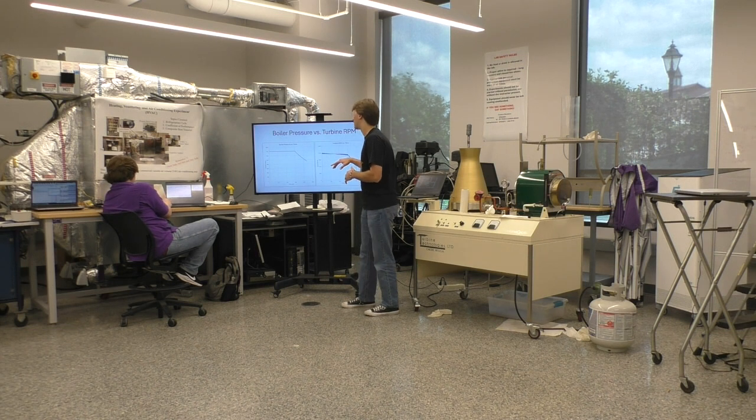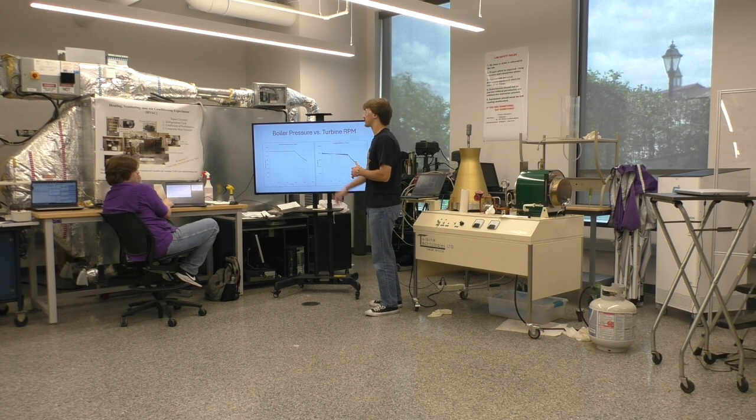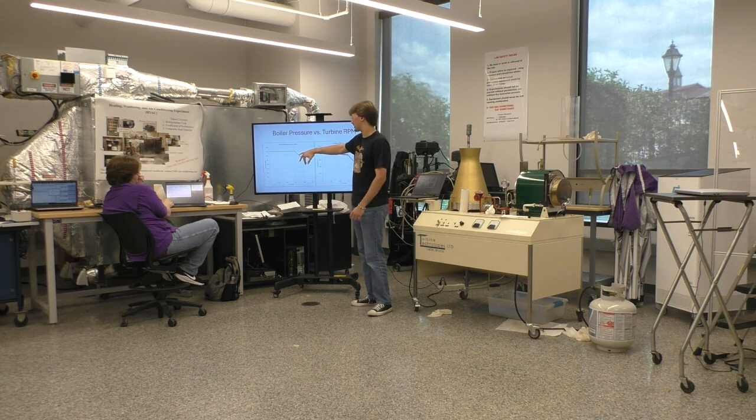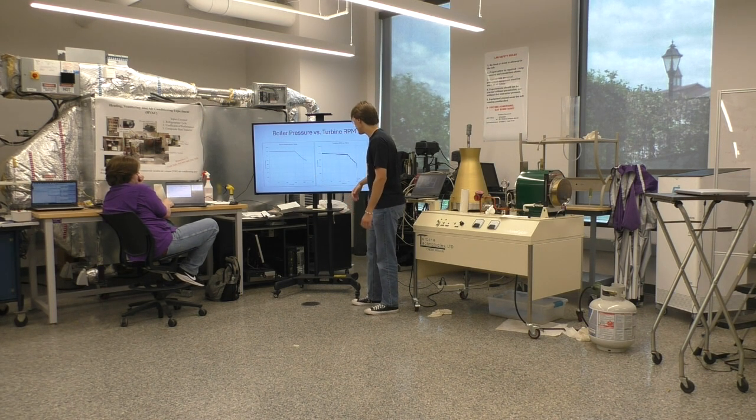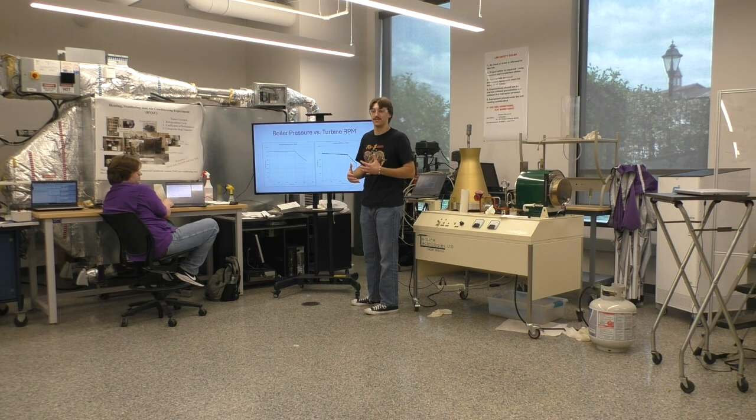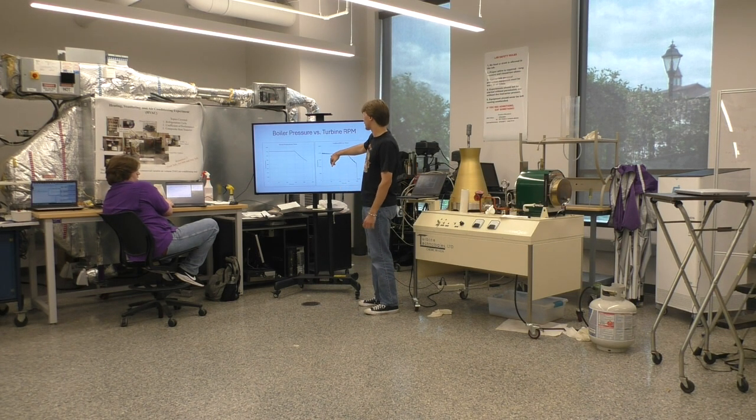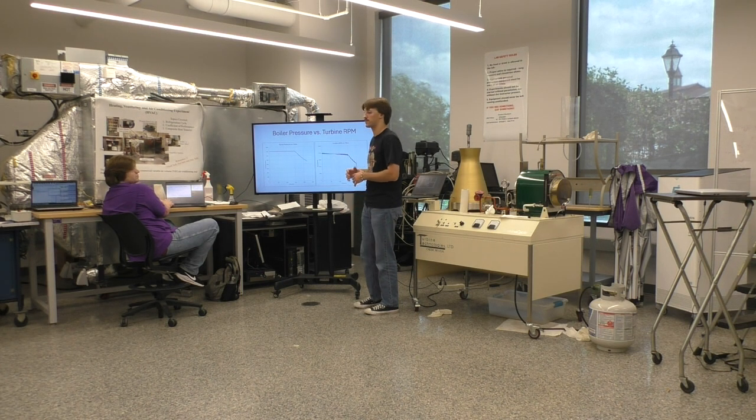And then now we have the boiler pressure and the turbine RPM. As you can see, as it sticks around that 700 kPa, the turbine is going to keep the same energy, right? And unfortunately, as you can see right here, it swiveled down before we shut it off.